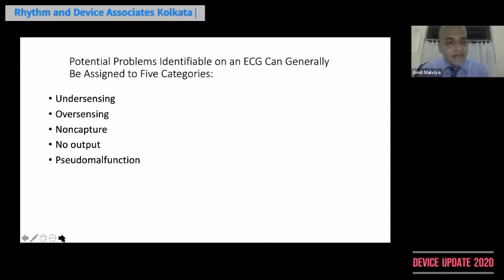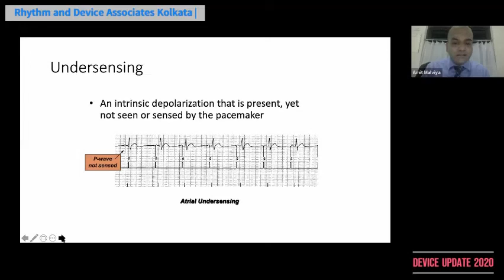So undersensing, to be very simple, is the failure of the pacemaker to identify an intrinsic depolarization. The depolarization is there in the heart, but the pacemaker does not identify it. As you can see in this ECG, there are P waves, but the pacemaker does not recognize the P wave and it continuously gives a pacing spike. So undersensing usually leads to over pacing. So this is very easy to understand.